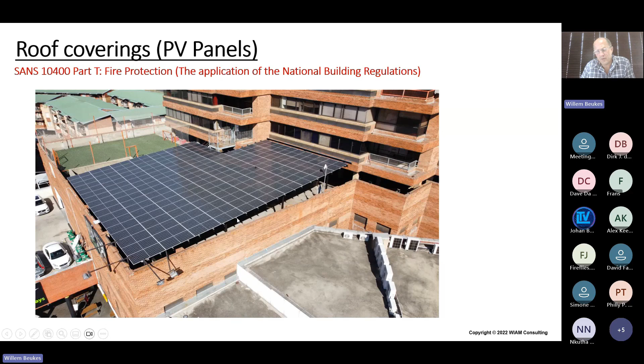In this case is a pure example of what I've just explained, where your PV panels are up to a section close to the windows. This is an installation in Pretoria. With the PV panels, there's no 5 meter horizontal gap between the window and the existing occupation. Yes, it's on a type of canopy carport structure, but you need to have a fire control section on this. On this section here, you also have a fire escape route, which can be compromised. In this scenario, you can see it wasn't designed and signed off as a rational design from a fire engineer concerning the PV installation.